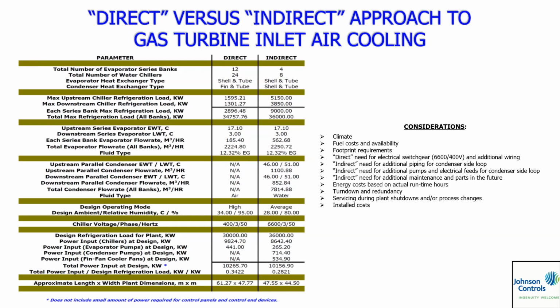The disadvantage with the direct, remember, we need a switch gear. We had to go actually 6,600 down to 400. So remember those step-down transformers. You got to have those. Indirect, however, you got the additional piping for the condenser water side. Fan coolers and all those condenser pumps and the electrical associated with it. All that stuff costs money. Indirect need for additional maintenance and parts in the future. All the cooling tower, the condenser fan cooler fans, the condenser pumps and the motors. All the hydronic specialties, more maintenance.